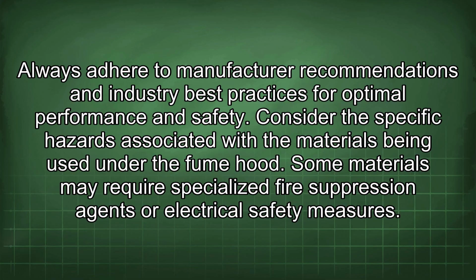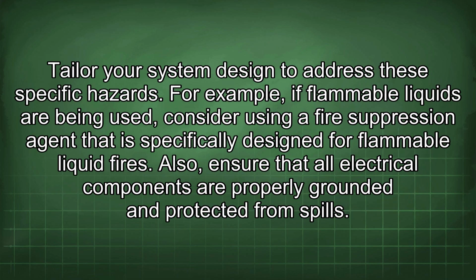Consider the specific hazards associated with the materials being used under the fume hood. Some materials may require specialized fire suppression agents or electrical safety measures. Tailor your system design to address these specific hazards. For example, if flammable liquids are being used, consider using a fire suppression agent that is specifically designed for flammable liquid fires. Also, ensure that all electrical components are properly grounded and protected from spills.